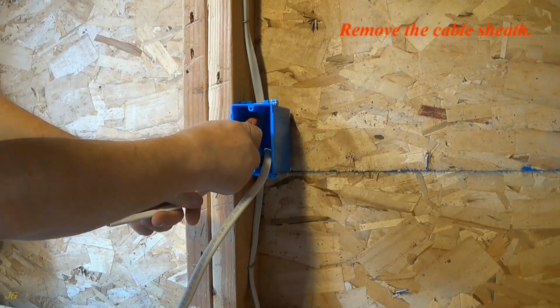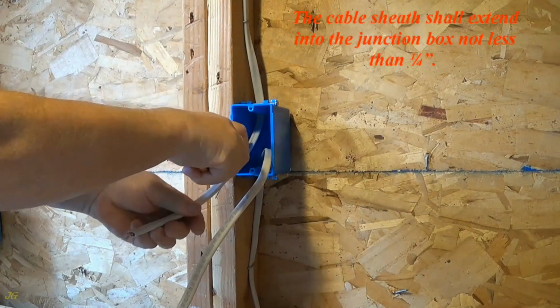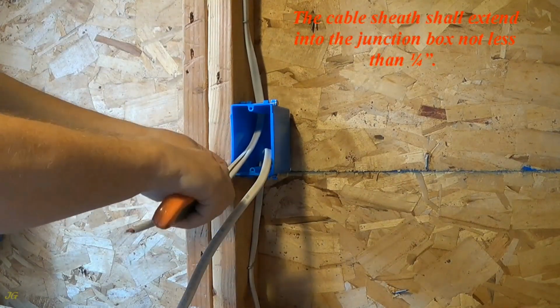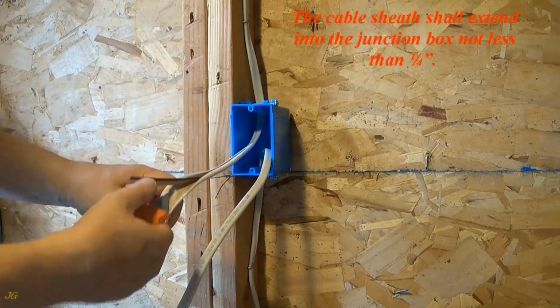Remove the cable sheath. The cable sheath shall extend into the junction box not less than 1/4 inch.